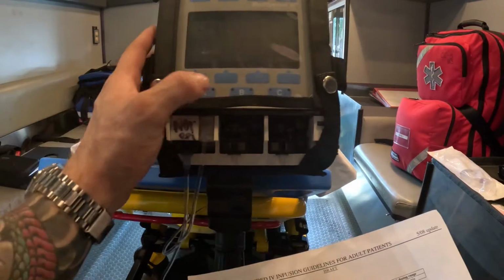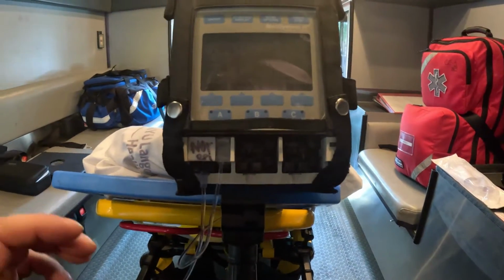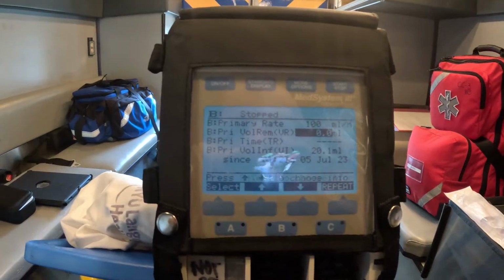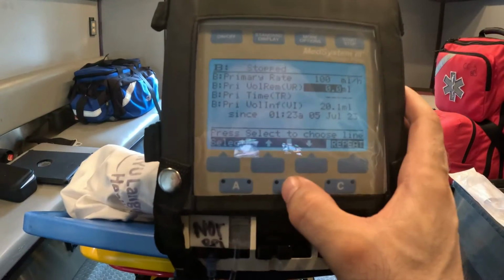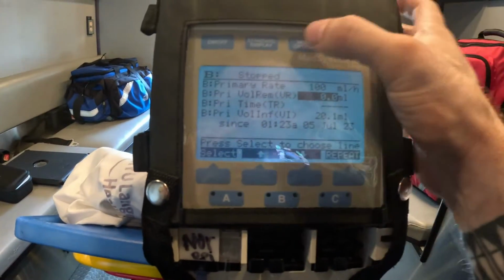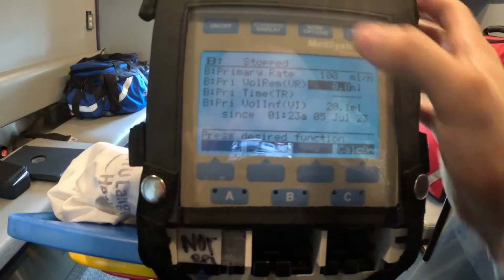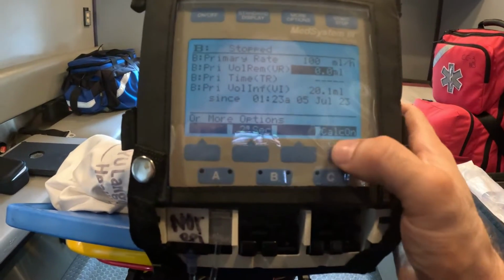We're going to set up a dose rate calculator, and the way you're going to do this, you're going to select your channel B. I'm now in my channel B, and then you're going to click here, this button says more options. So just to go back, select channel B, and then click more options. Once I click more options, you see at the bottom there's something that appears, calc on. I'm going to click this on.